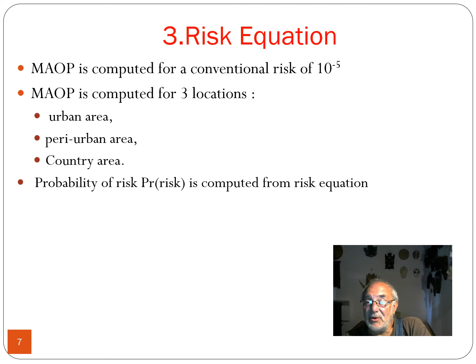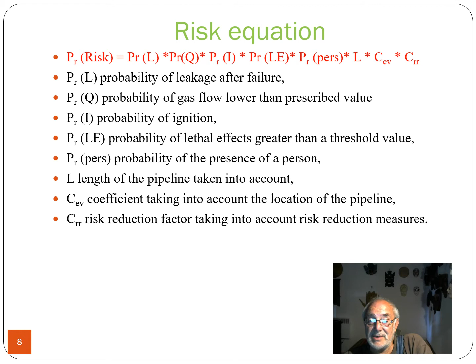The risk equation consists of 8 terms, where PR de L is the probability of leakage after failure, PR of Q is the probability of a gas flow lower than the prescribed value, PR de I is the probability of ignition, PR de LE is the probability of lethal effect greater than the threshold value, PR pers is the probability of the presence of a person, L is the length of the pipeline taken into account, C subscript ev is the coefficient to take into account the location of the pipeline, and CR is the risk reduction factor taking into account risk reduction measures.